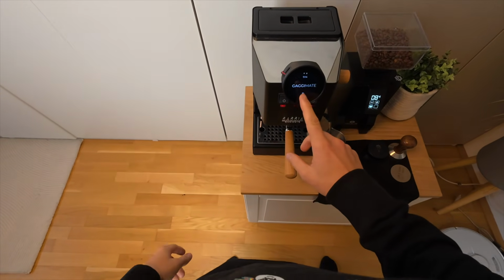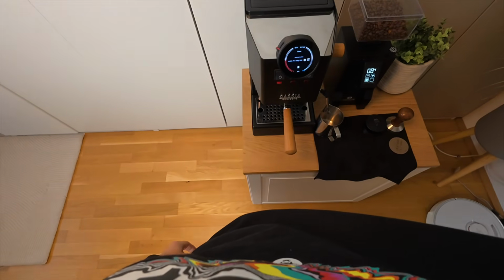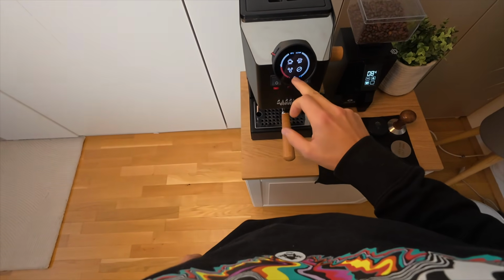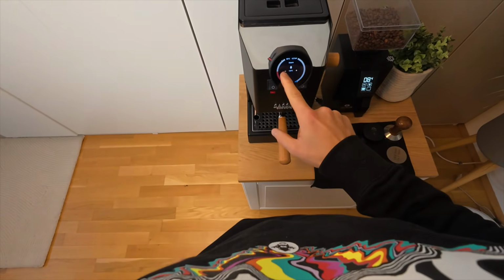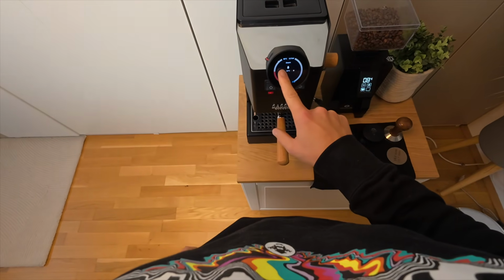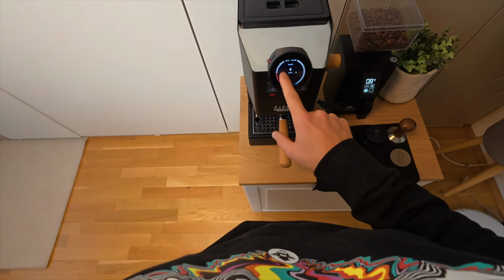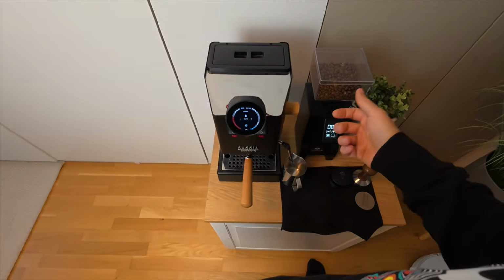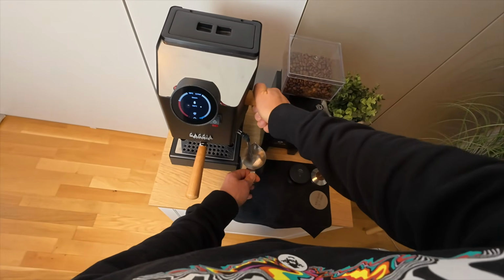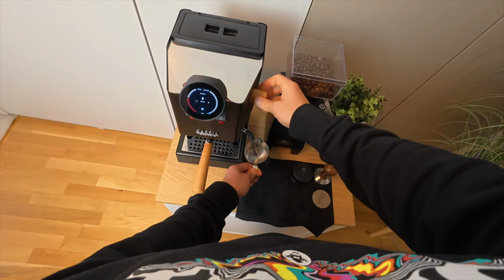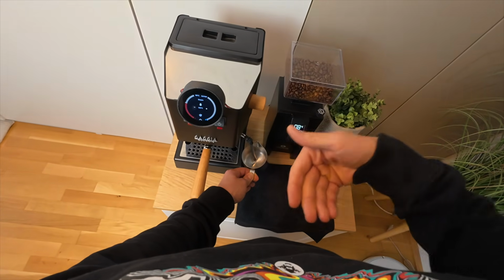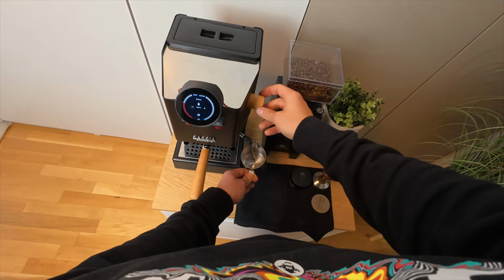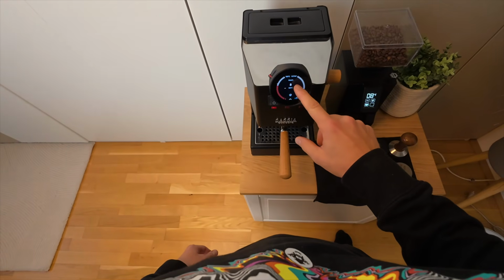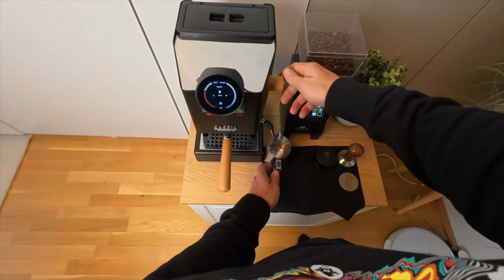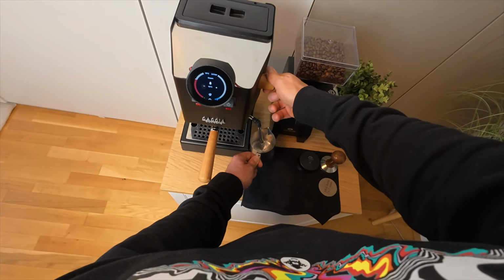For calibrating the temperature, we do the following: go to steam mode and start with, I don't know, like 100 degrees. Wait a little bit and check if steam comes out. If not, increase the temperature, going to 110, wait a little, then check again for steam.